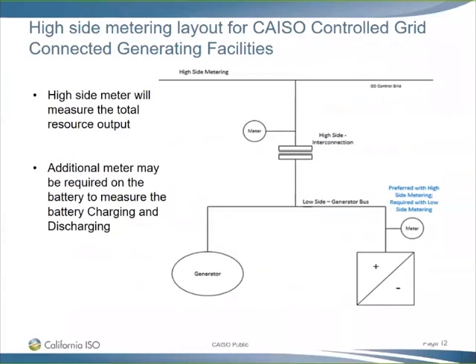So if you see the slide, there is a second bullet item on the left side. It says additional meter may be required. Under the single resource ID, we need only one meter for the net output. But if there is any need, as Chris also mentioned earlier, for RPS or WREGIS reporting purposes, we may need an additional meter, and we'll talk about that in detail in upcoming slides. So for settlement purposes, ISO settlement purposes, only one meter is enough. But if the resource would like to participate in WREGIS or needs any other type of configuration, we may require additional metering.